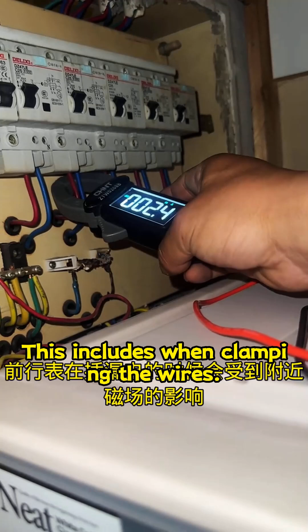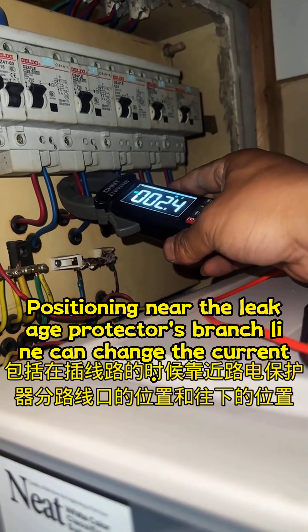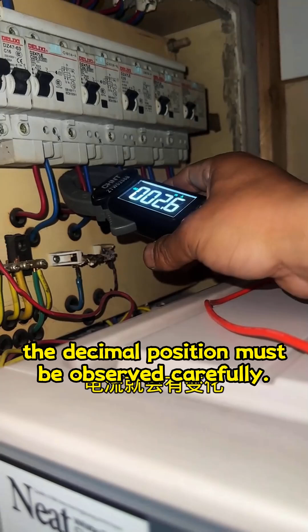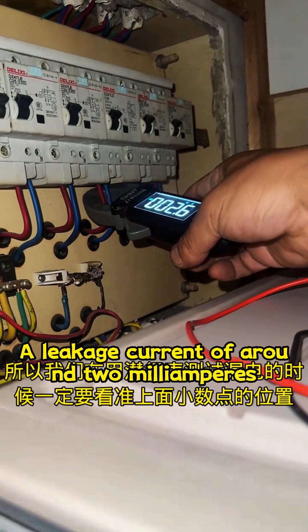Also observe the load behind it. Clamp meters can be affected by nearby magnetic fields. This includes when clamping the wires. Positioning near the leakage protector's branch line can change the current. Therefore, when using a clamp meter for leakage testing, the decimal position must be observed carefully. A leakage current of around 2 milliamperes is a normal phenomenon.